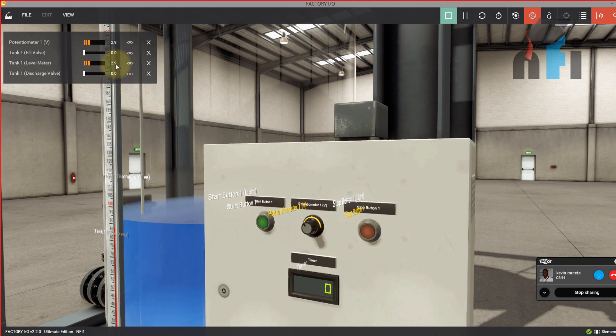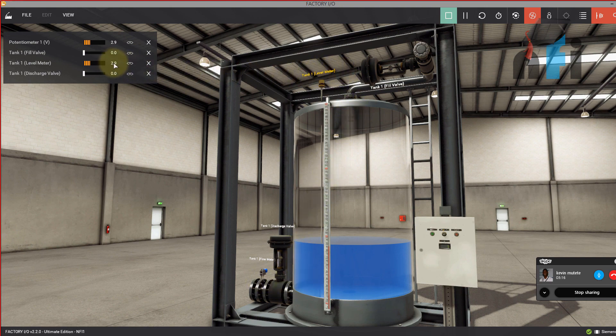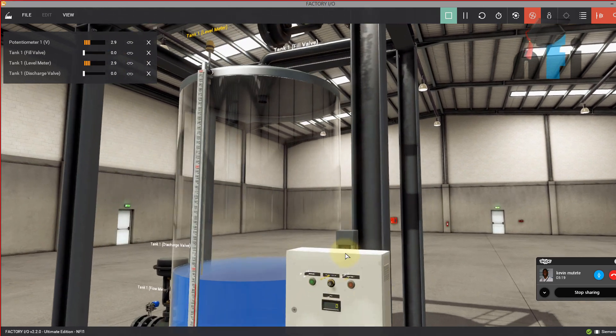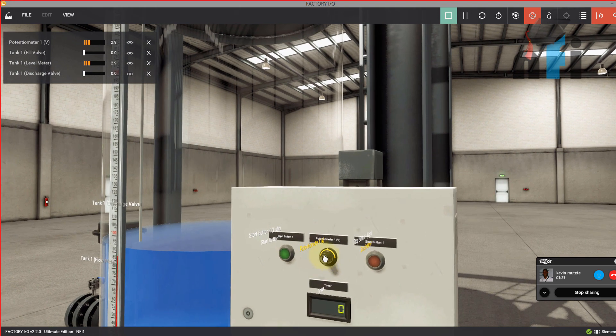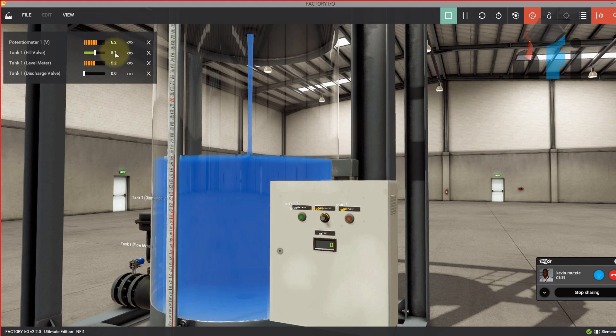Right now the level is at 2.9 and this potentiometer is my set point. The fill valve is 0% open (closed) and the discharge valve is also 0% open (closed). We have filling from the top and discharge from the bottom. There is a level meter indicating 2.9, which means 29%. Now if I increase my set point to 6.2, you will see the valve is 100% open and as the level reaches the set point the valve proportionally decreases.